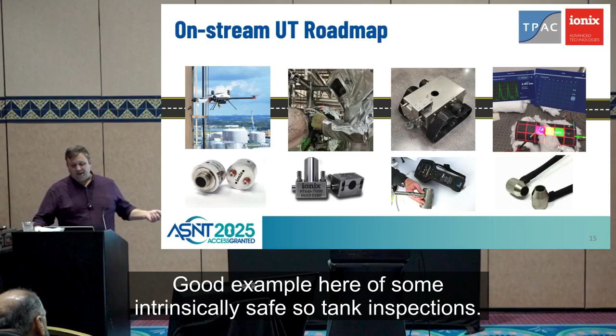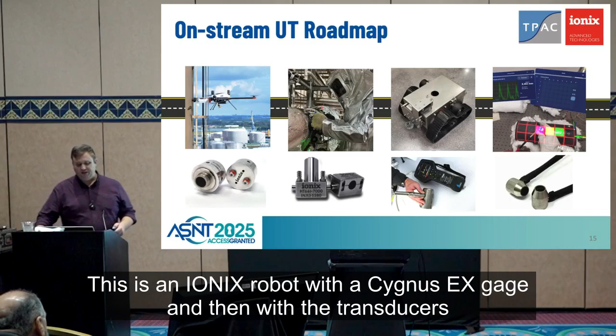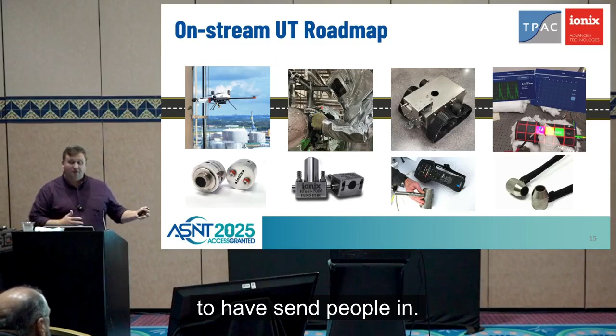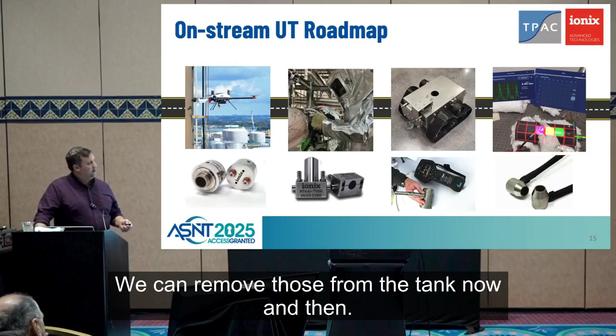Good example here of some intrinsically safe tank inspections. This is an IONIX robot with a Cygnus EX gage, and then with the transducers on there as well. So it's an entirely intrinsically safe package. We're able to access those areas that typically would have to send people in, and we can remove those people from the tank now.